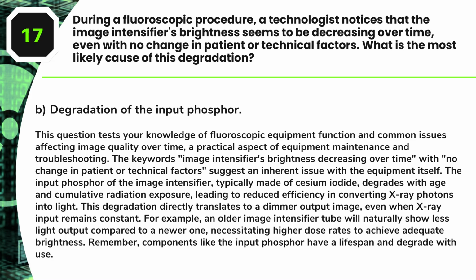Answer, B. Degradation of the input phosphor. This question tests your knowledge of fluoroscopic equipment function and common issues affecting image quality over time, a practical aspect of equipment maintenance and troubleshooting.